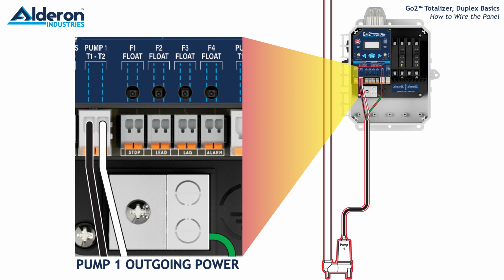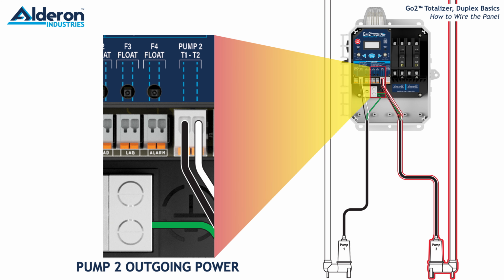Install the T1 and T2 from the pump 1 outgoing power circuit to the pump 1 T1 and T2 terminals on the Go2 Totalizer circuit board, and install the ground wire to the ground lug. Install the T1 and T2 from the pump 2 outgoing power circuit to the pump 2 T1 and T2 terminals on the Go2 Totalizer circuit board, and install the ground wire to the ground lug. Note, the pumps must contain integral thermal overload protection.